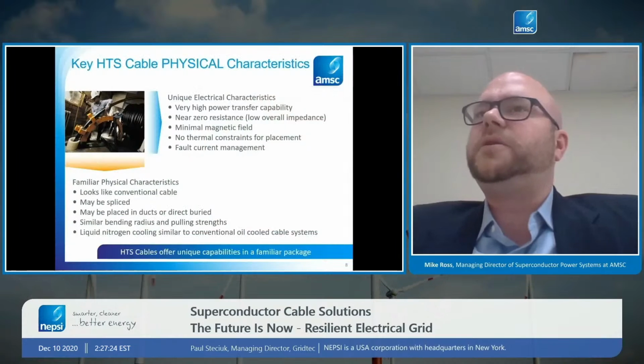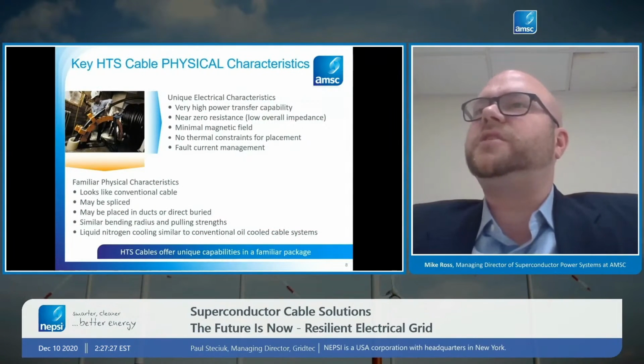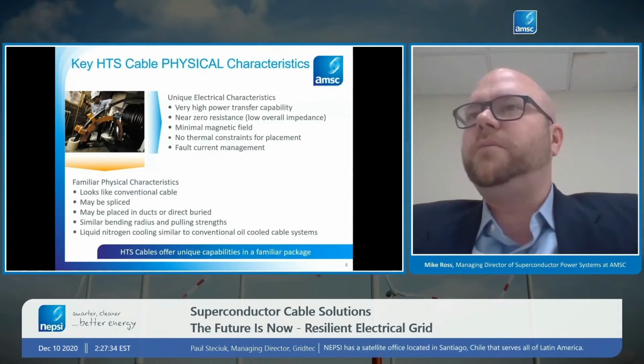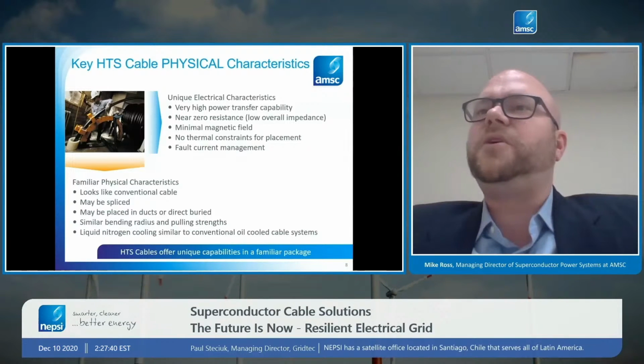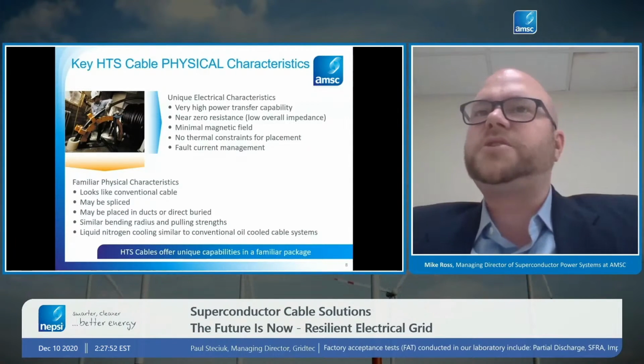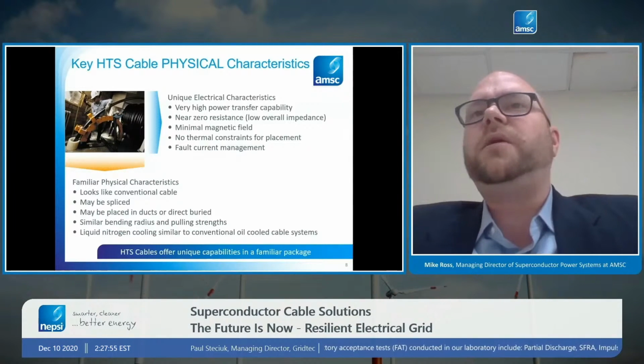So we have these cables now, and the cables have these very unique characteristics. Very high power transfer capability, basically zero resistance, no EMF, no thermal constraints for placing, no heat exchange, and this fault current management. They physically look like conventional cables. That's in the top left-hand corner. No expert in power cables would ever know that that's a superconductor cable and not a conventional cable. They look exactly the same. The cables can be spliced. So we get about 15 to 1600 feet on a standard cable reel, and then you splice those cables together to get to whatever length that you want, as you would with any conventional cable.